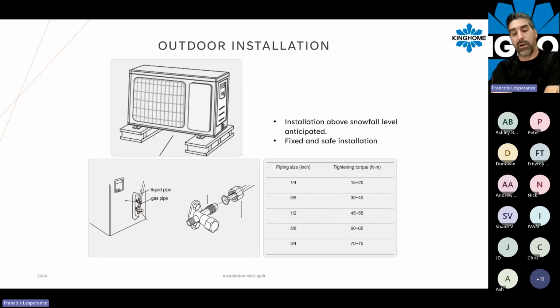Also, because those systems are heat pump systems and they will run all winter long, it's good to have the unit installed above the snowfall level, because we don't want an obstruction or restriction due to an accumulation of ice or snow in front of the unit or in the coil directly. Also, if you do a repair on a leak and you have to redo the flare connection, make sure you use a torque wrench to do your connection, so you will not face another leak because the connection is too weak.